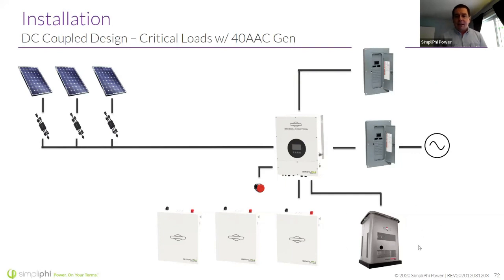Oh, what's this down here? This is a Briggs & Stratton generator. This is a great way, if your homeowner has a standby generator—what happens when an outage comes along? That generator runs the entire time the power is out, so there's a lot of runtime and a lot of noise. A great concept is to pair a generator with energy storage. That enables you to run the generator to refill the bank, then let the generator rest for some peace and quiet. When the inverter sees that the batteries are hitting their set points, it calls the generator back to action, all while you're continuing to feed your backed-up load center.